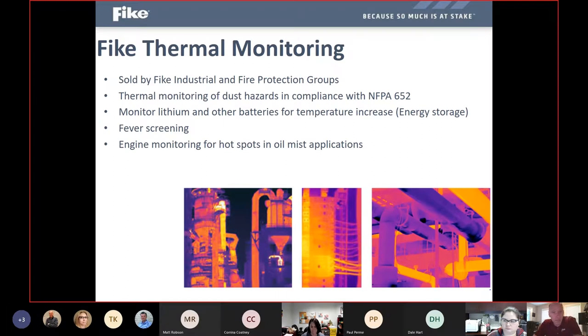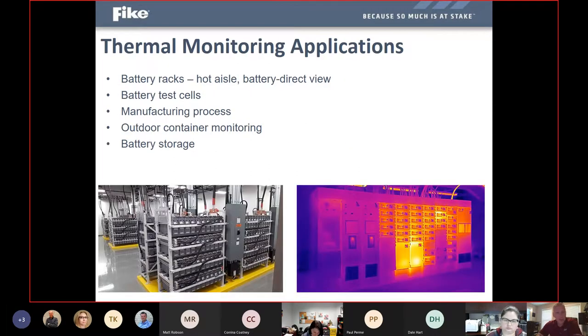As that has evolved over the last couple of years, we have added on to that with some additional types of detectors, one of which is thermal monitoring. Thermal monitoring is now required in the NFPA 652 code for combustible dust hazards. We're also seeing a lot of popularity and demand for this technology with energy storage systems, especially with the recent popularity of energy storage systems for lithium ion batteries. The thermal monitoring of those battery racks or enclosures is becoming very popular because we want to detect thermal runaway or a battery failure very early in the process, before it might start to cascade to additional racks or assemblies of batteries and destroy the entire enclosure.